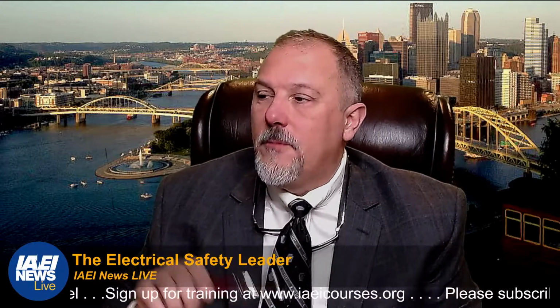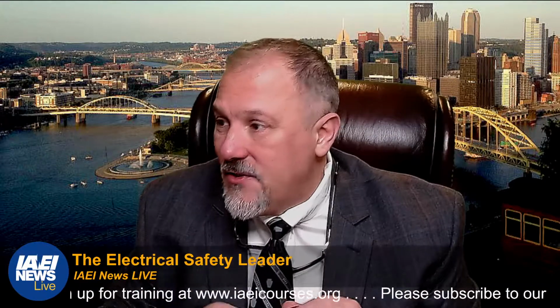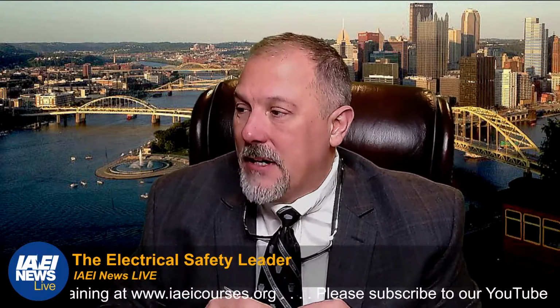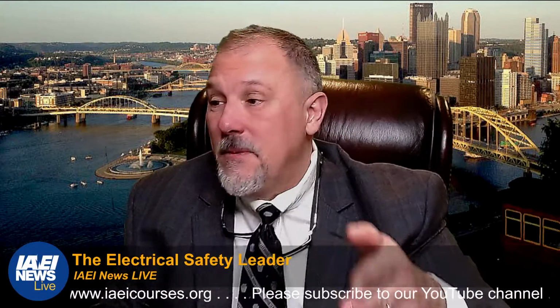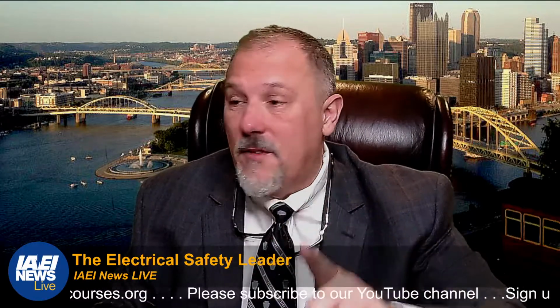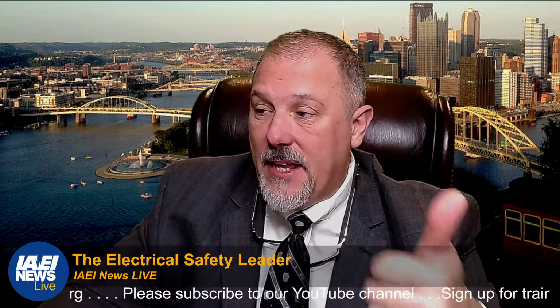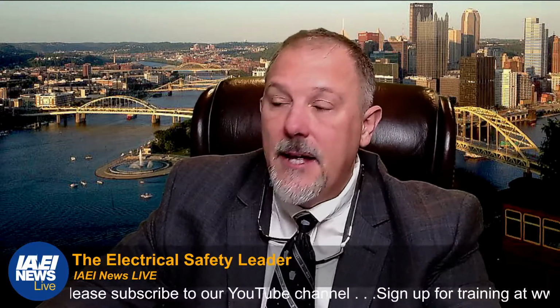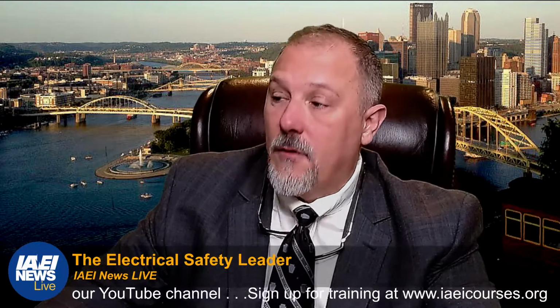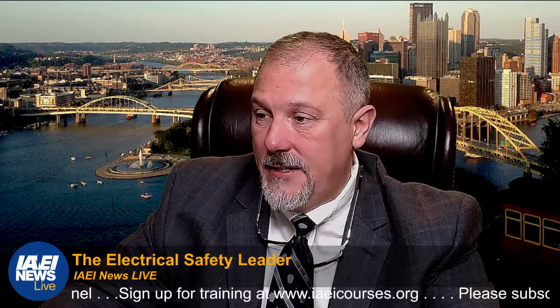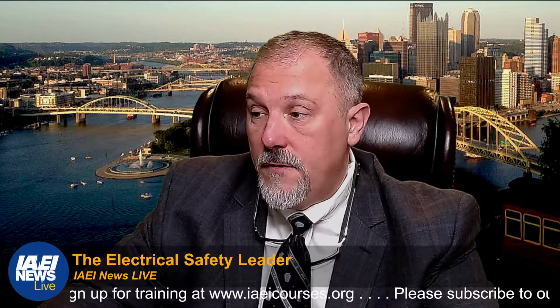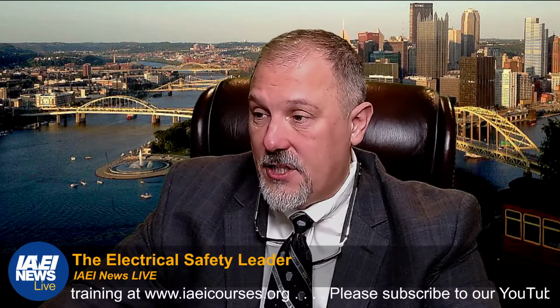The servicing and electrical preventative maintenance shall be performed using identified replacement parts that are verified under applicable product standards. The replacement parts shall comply with at least one of the following: A, be provided by the original equipment manufacturer. B, be designed by an engineer experienced in the design of replacement parts for the type of equipment being serviced or maintained. C, be approved by the authority having jurisdiction.